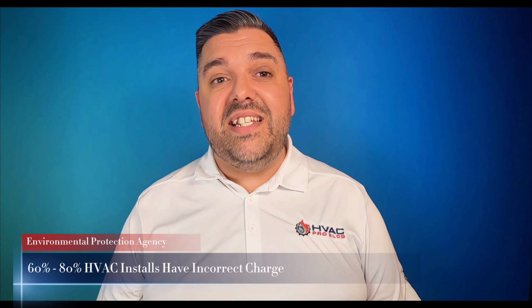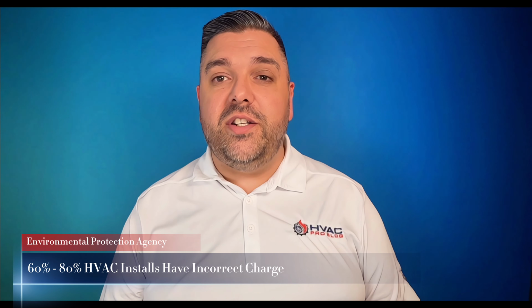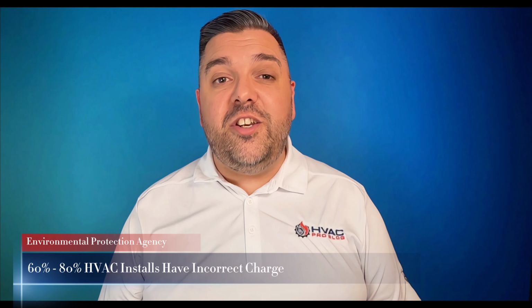Of course, installation quality is where theory crashes into reality and the numbers are ugly. The EPA estimates that 60 to 80% of installed HVAC systems have incorrect refrigerant charge. A study published in ASHRAE Transactions found that just 10% undercharge reduces cooling capacity by 7% and increases energy consumption by 5%. Overcharging is even worse. 20% overcharge can increase energy consumption by 12% while also reducing capacity.